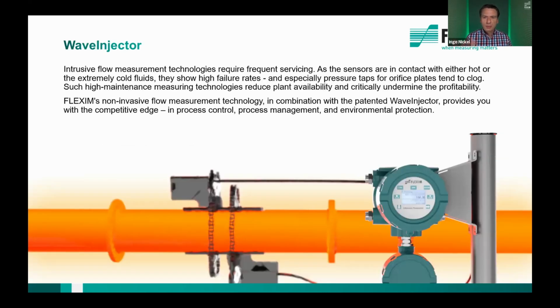And as I mentioned, we have a dedicated mounting system, which can be used for extremely low, but also extremely high temperatures. It's called the wave injector. The wave injector, along with the ultrasonic transducers, is simply installed on the outer surface of the pipe using some coupling plates for proper acoustic contact. This means we have a very sophisticated solution for very extreme temperatures.